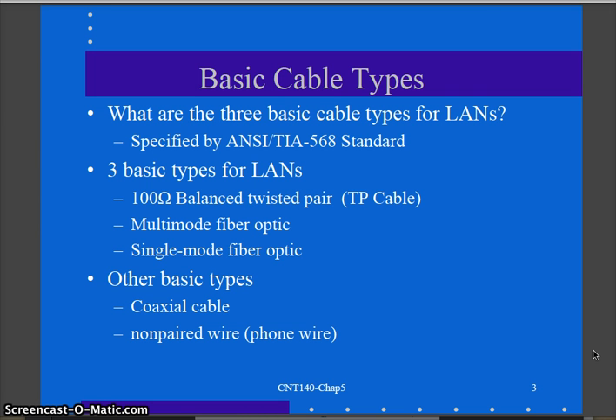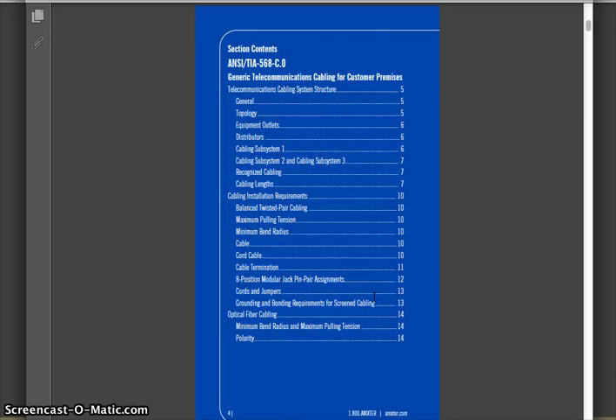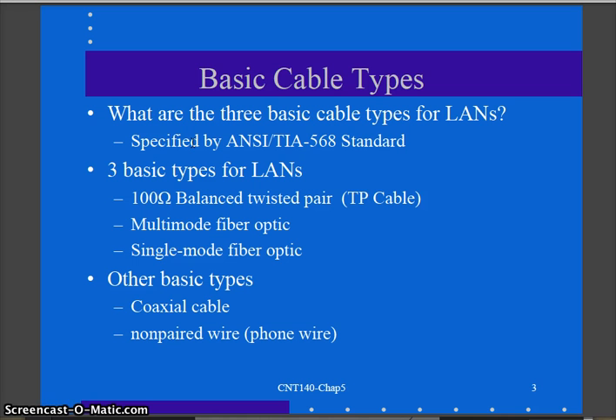The basic cable types found in LANs are specified in the ANSI/TIA 568 standard. Looking at the 568 C.0 part of the standard around page seven, the recognized cabling types are: 100-ohm balanced twisted pair — what we'd consider unshielded twisted pair or CAT5 cabling — multimode fiber, and single-mode fiber. Those are the three accepted types of cabling for use in LANs.